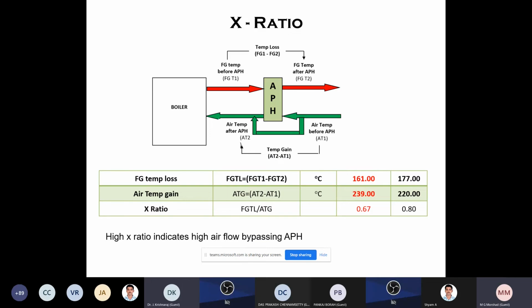Now, another factor is called the X ratio. What will happen in such a case? The air will not enter here. It will bypass and go. So that is also a loss of efficiency of the boiler. So this is called the X ratio.